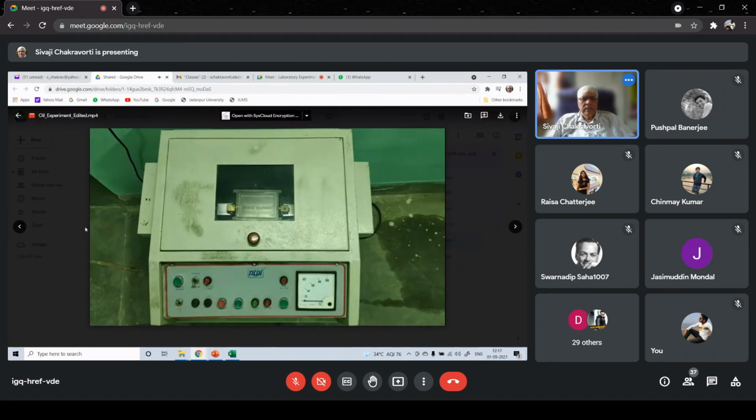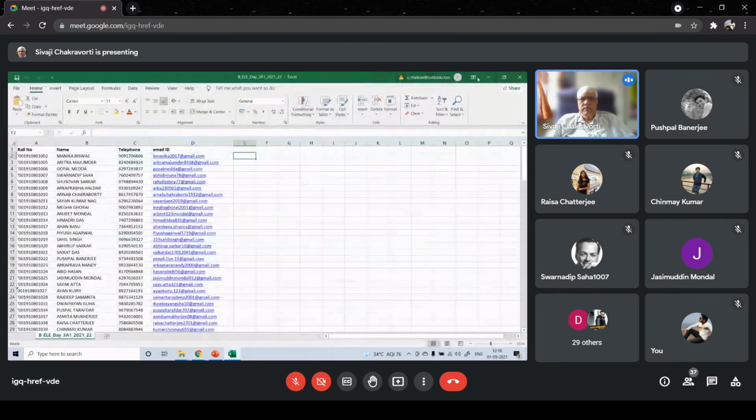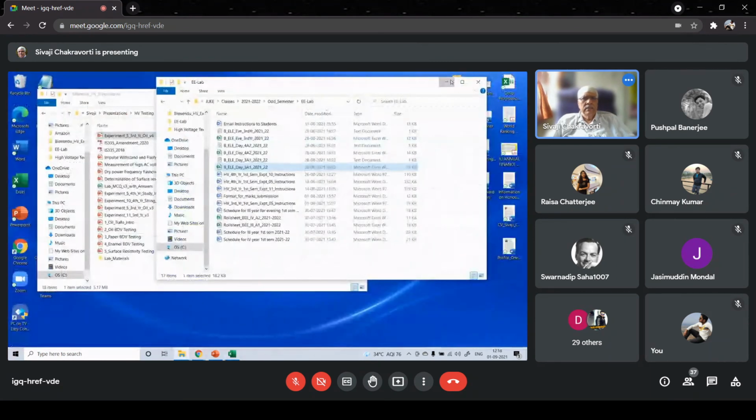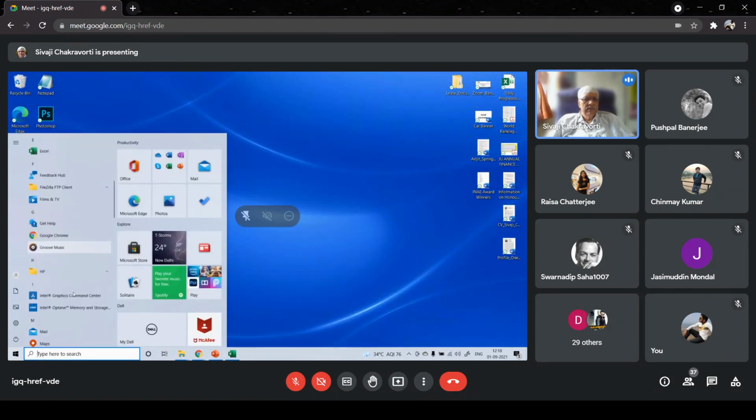And after that, you have to open this top cover, take out this one. If there is any gas bubble, use the stirrer, remove gas bubbles, and then you do the test again after 2 minutes. In this way, 6 readings have to be taken. So this is another video, and there is a software demo also, although not very smart, but quite okay. Let me show you that one.